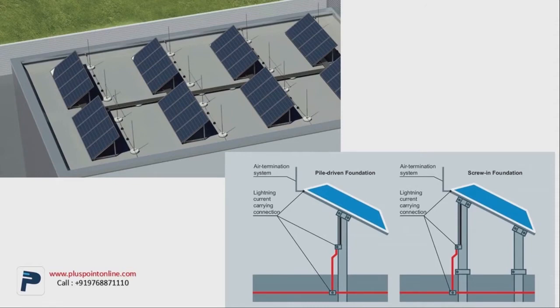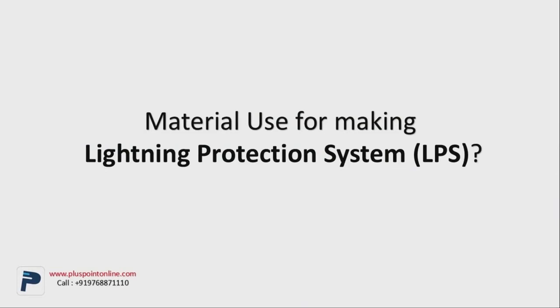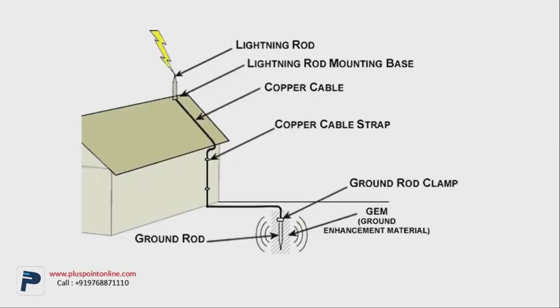The material used for making the lightning protection system, I'll explain the different kinds of materials which are used. Basically, the first thing that we require is a lightning rod. As you can see on the top, that's the lightning rod. Where the lightning rod is set up, the base needs to be the mounting base. With that, you need a copper cable, and to tighten the cable to the wall, you require cable straps. The most important element of the system is the grounding.